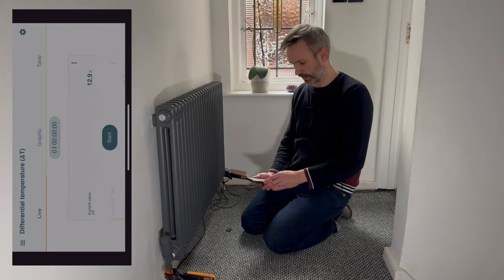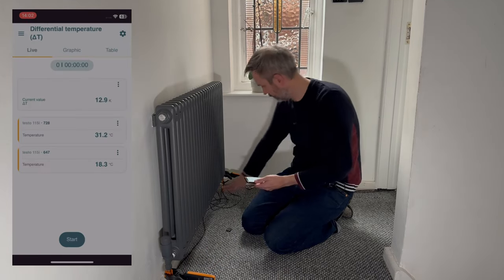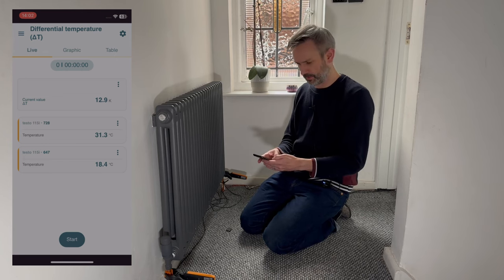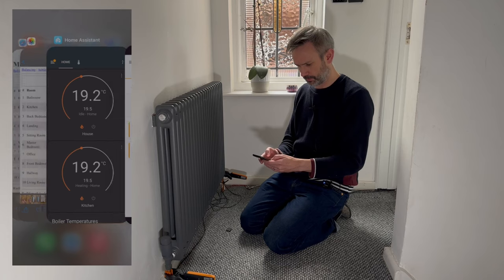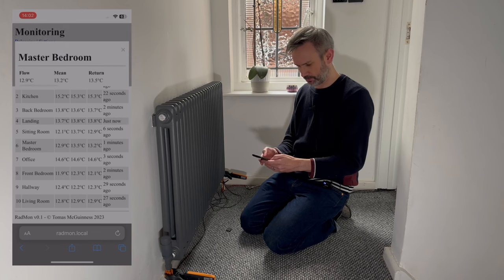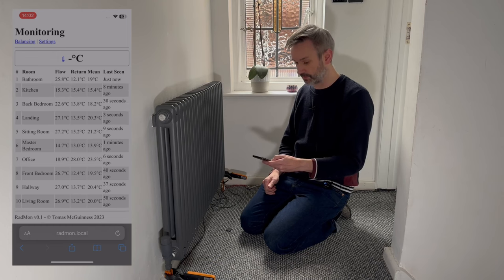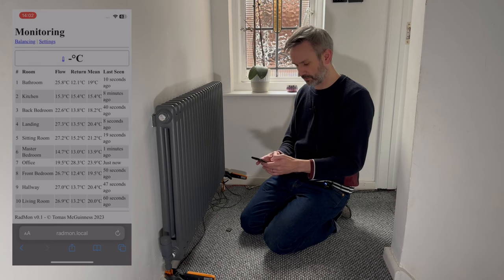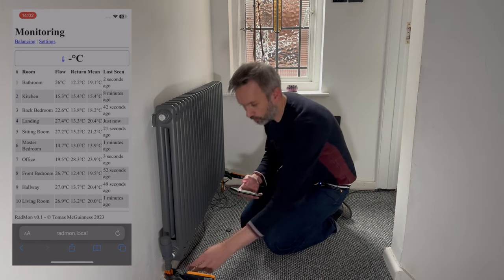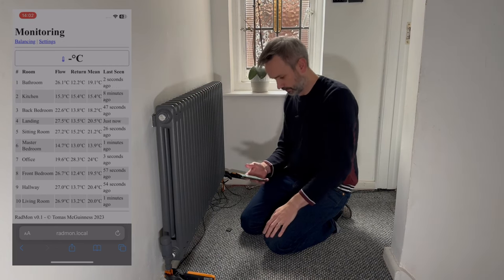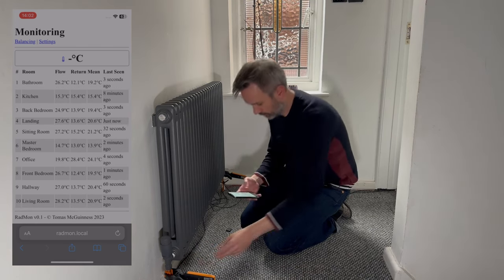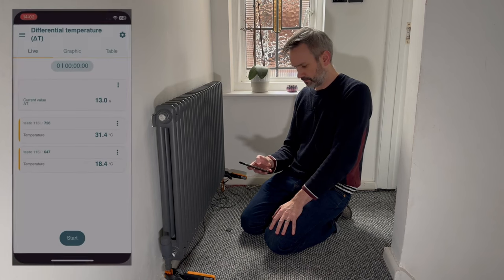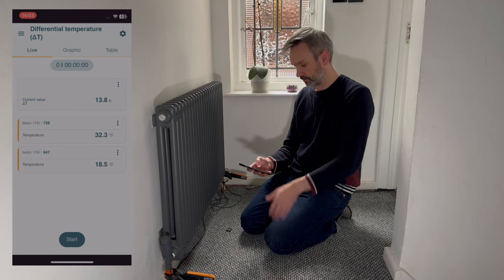All right, so I'm back in the hallway now. And as I can see on the app, one of these is now heated up. So this one over here, so this must be the flow. So this clamp here is reporting 31.3 and I'll jump over to my display. Let me just refresh this. The landing, it's only reporting 27.3. So that is quite a difference. We do have 13.5 on the other side, so it's definitely not registering any warm up there. And this is a cast iron rad, so this will take a bit of time before we start getting any heat coming out the other end. The return hasn't really moved, which is the same, but the actual flow temperature is much, much higher.